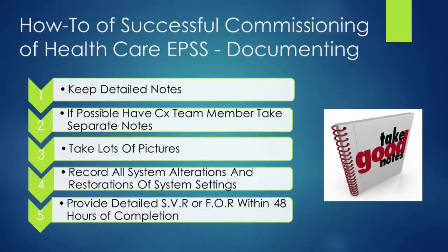That has happened, and I documented it in a report, and I clearly told our clients and the maintenance staff, when you operate it this way, make sure you have a sequence or a method of procedure to make sure these are always set right, because if they just get inadvertently switched one way or the other, this is what can happen. About 12 months after I did testing on a facility, I got a call: we did this testing, we lost some of our ATSs, and we're really concerned. Did we miss something when we were testing?